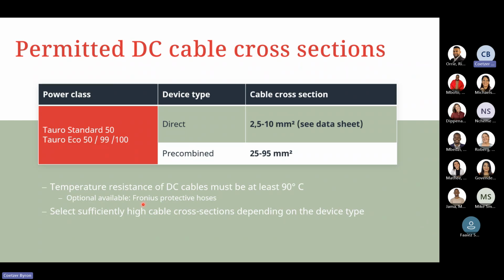Lastly, the permitted DC cable cross sections. If you are using the Fronius Tauro Standard 50 kilowatt variant and doing a direct connection coming in, we can use 2.5 to 10 mm squared, but please always see the data sheet to confirm what cable sizes you can use depending on the variant that you're using.